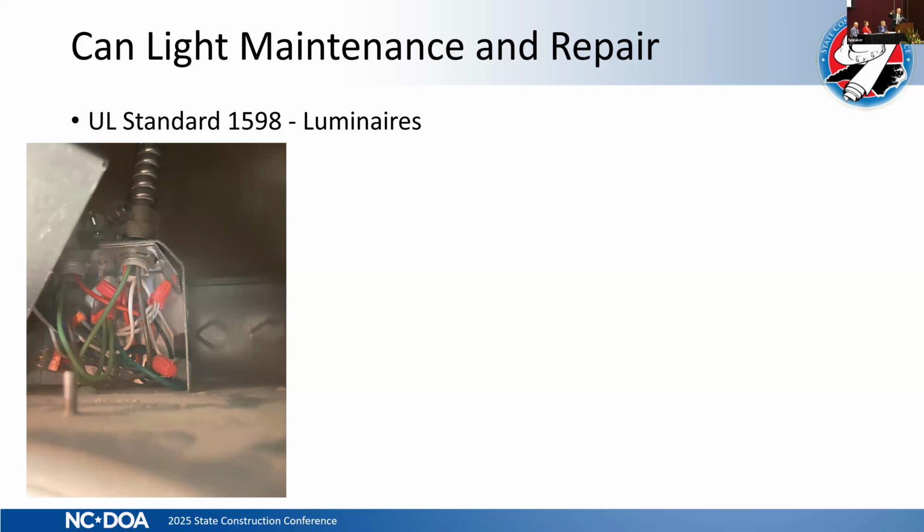And once you realize, okay, we've done this for a long time. We were doing it with fluorescents. We assumed it was like a fluorescent, except now it's an LED. It has different parts, and for some reason, they moved the box. The box isn't at the edge. I don't know why. I think most we have found are at least 3 inches to 5 inches away from the aperture.